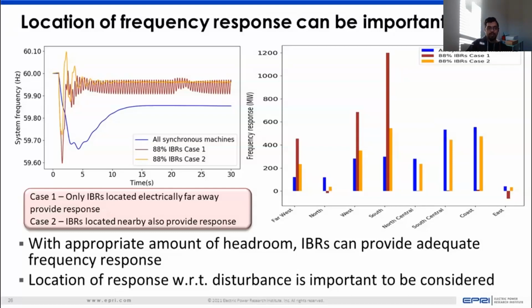Take the scenario where, granted, you can get a better or faster frequency response when 88% of the fleet is inverter-based resources. In case one, the frequency response comes from an electrically far away region, and in case two, from an electrically close by region. Devices from an electrically far away region have to provide much more response, which means you have to plan for that capacity being available, you need that level of headroom available if they have to come up from far away resources.